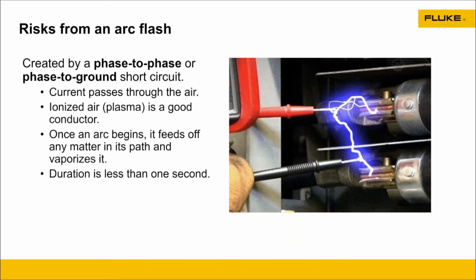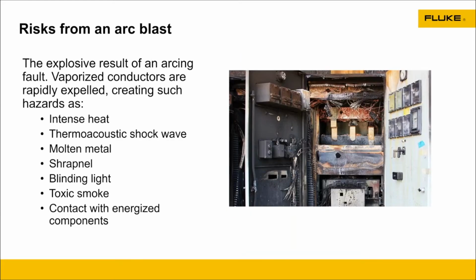And these happen within less than a second. This is where all that matter and all that vaporization takes place. From that arc, we can have an arc blast. Now that arc blast becomes explosive in nature at that point. You can see in this cabinet there, that arc blast, because of that potential energy, there's intense heat involved with that. Obviously, a shock wave of energy is running through because of the amount of intense heat.